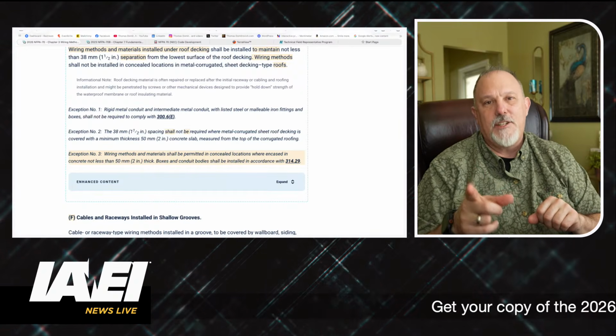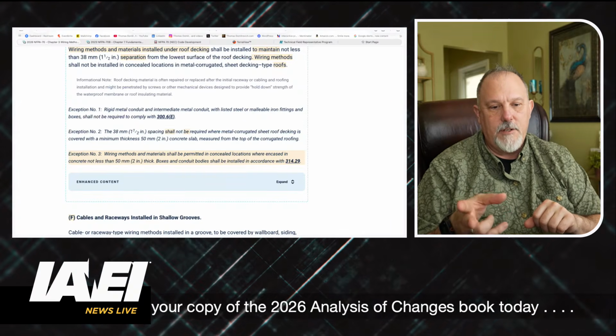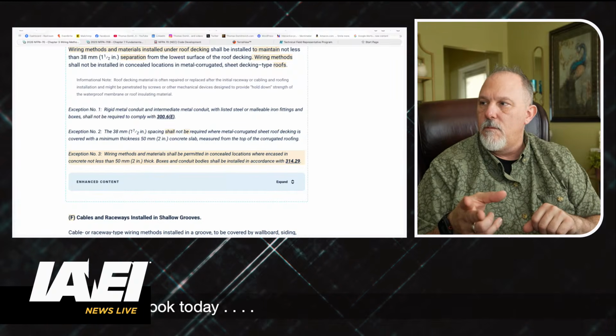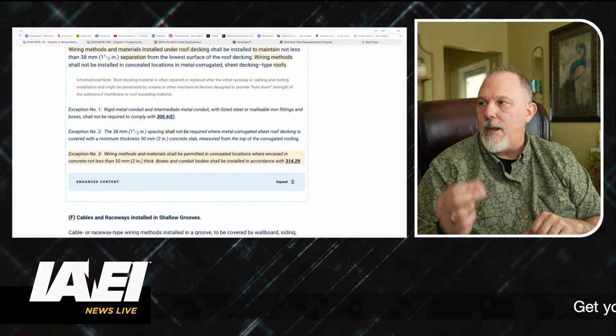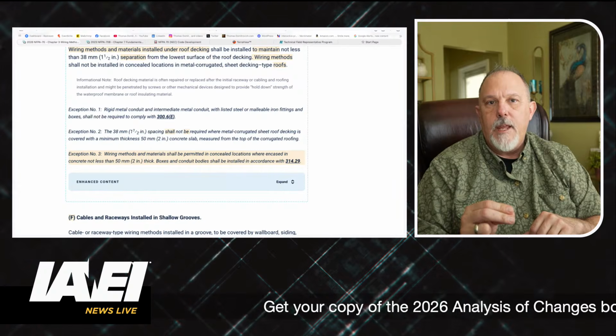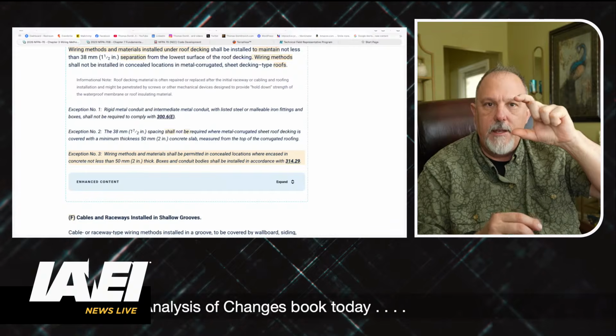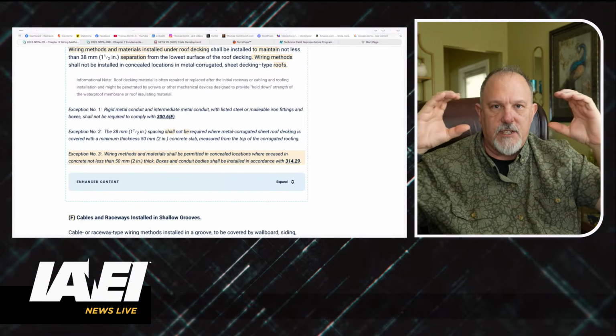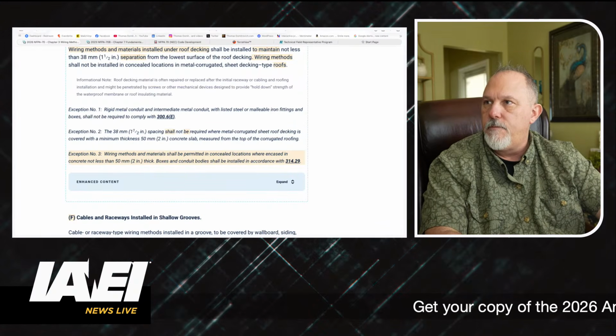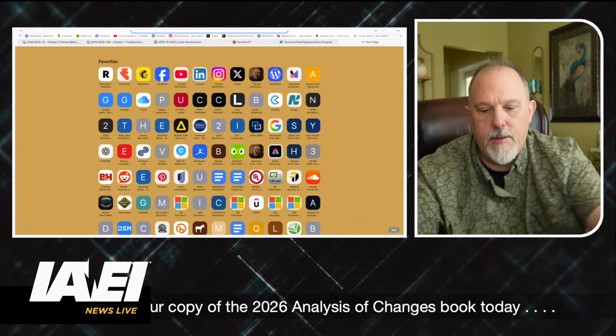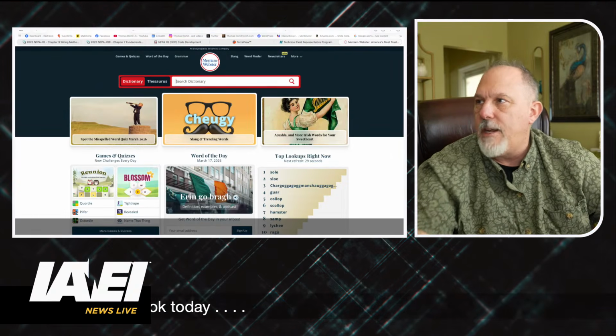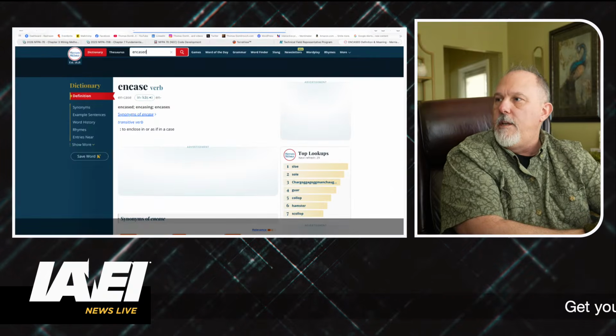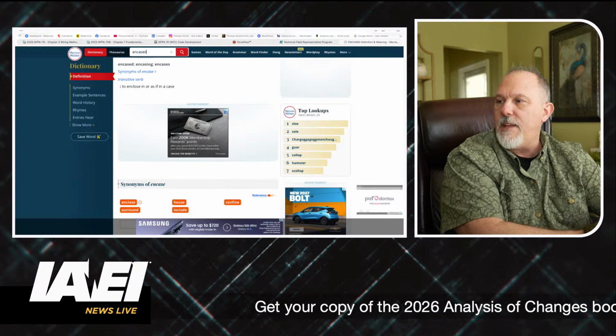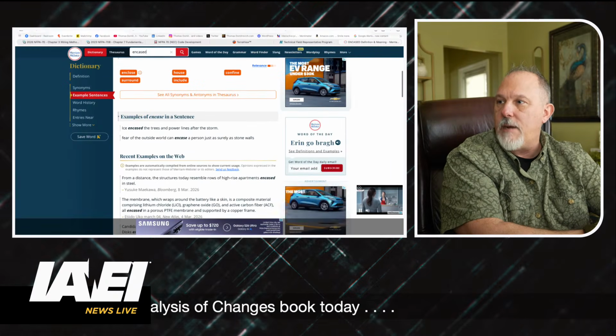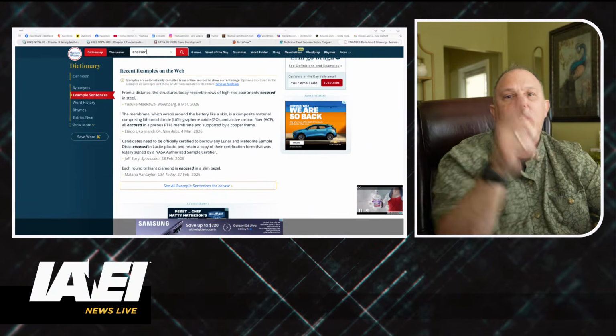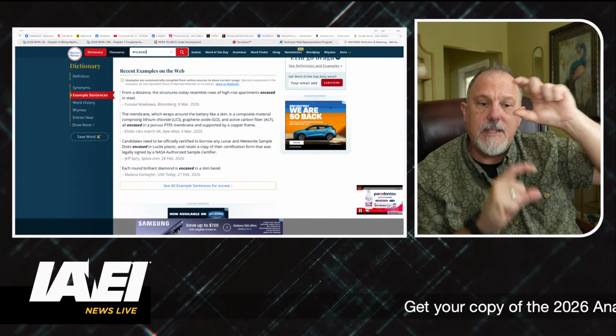Here's my issue. Let me ask you a question, Willie and Robert. When I say encased in concrete not less than 2 inches thick, if I have a 2-inch thick raceway and I have 2 inches worth of concrete on either side of it, that wouldn't be encased, would it? Let's do Merriam-Webster. Encased: to enclose in or as if in a case. Ice encased the trees and power lines after the storm. So here's my question. Do I need 2 inches on top and bottom of the raceway to say it is encased?